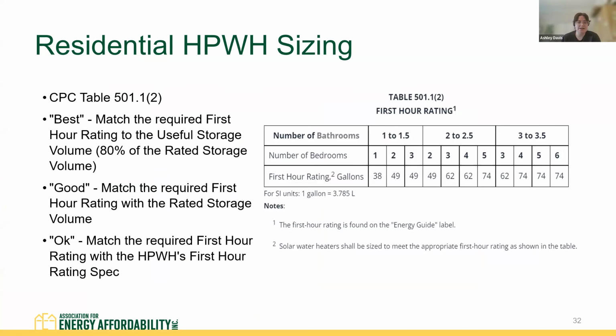Another design consideration is to think about sizing. I'm sure many of you are used to sizing gas water heaters with this table. This is from the California Plumbing Code, and it basically provides the first hour rating that is required for your water heater, dependent on the number of bedrooms and bathrooms that the water heater is serving. However, like Ari mentioned, heat pump water heaters are much slower to recover than gas tank type water heaters. And so that means you probably want to go above and beyond what this table requires to ensure that you're going to have a good amount of continued hot water access, right?